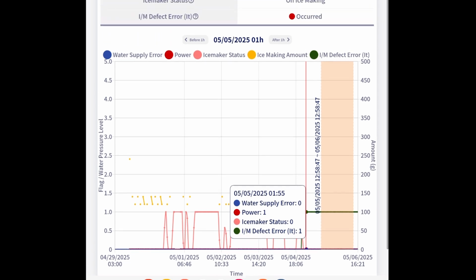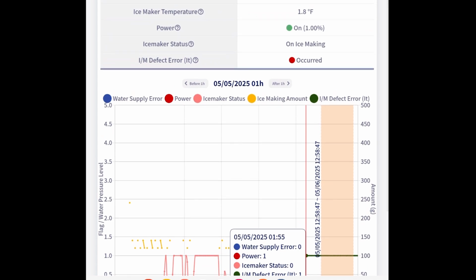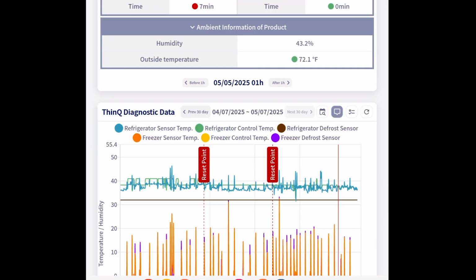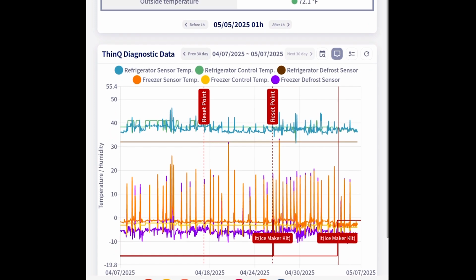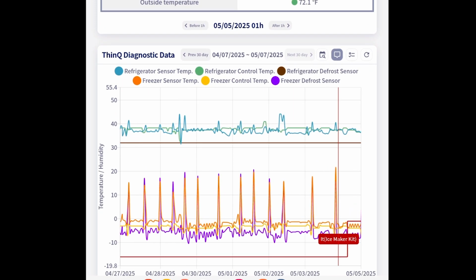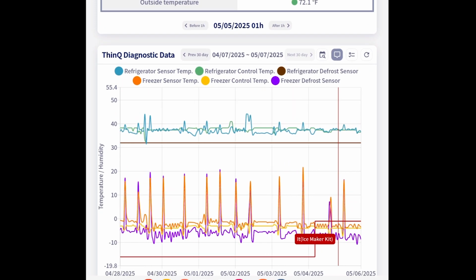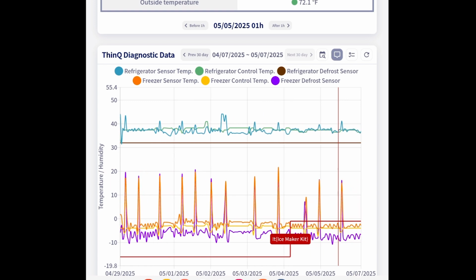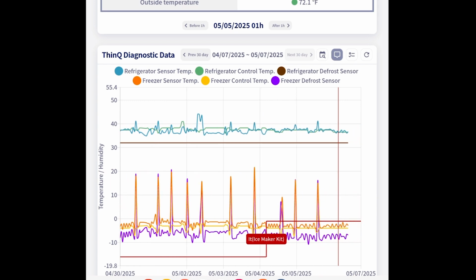The other thing that you can do for error codes is if you go back to your cooling cap tab and you look at your cooling chart, there it specifically says IT error code in the same places that we saw it on the ice maker graph. So you can see it in both tabs. So that's how IT error code will display for ice maker.